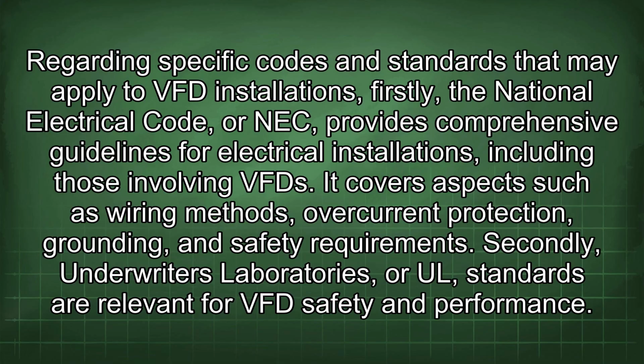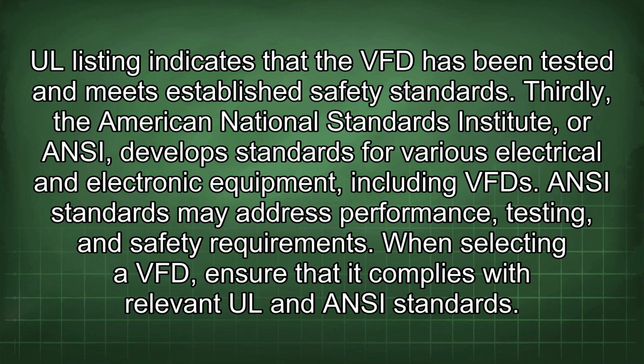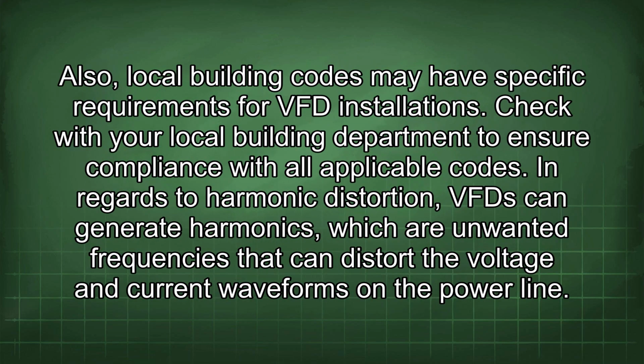Secondly, Underwriters Laboratories, or UL, standards are relevant for VFD safety and performance. UL listing indicates that the VFD has been tested and meets established safety standards. Thirdly, the American National Standards Institute, or ANSI, develops standards for various electrical and electronic equipment, including VFD. ANSI standards may address performance testing and safety requirements. When selecting a VFD, ensure that it complies with relevant UL and ANSI standards. Also, local building codes may have specific requirements for VFD installations. Check with your local building department to ensure compliance with all applicable codes.